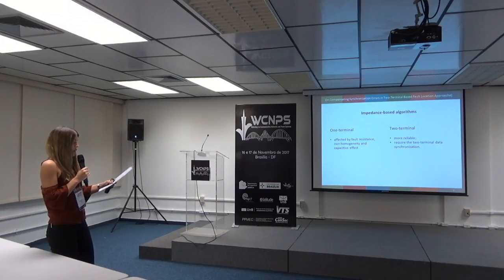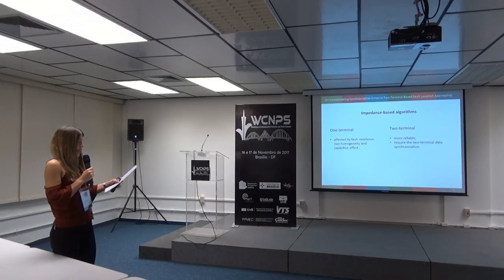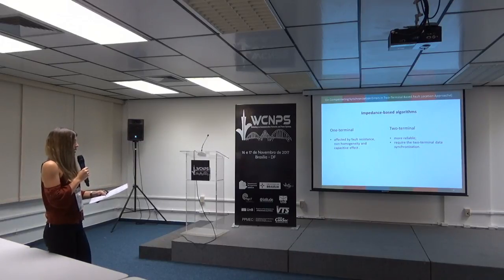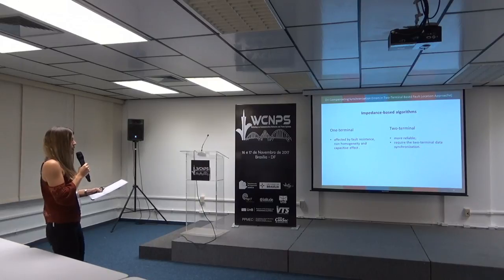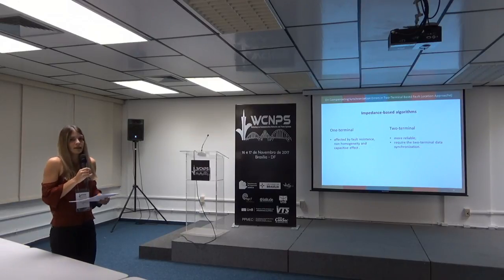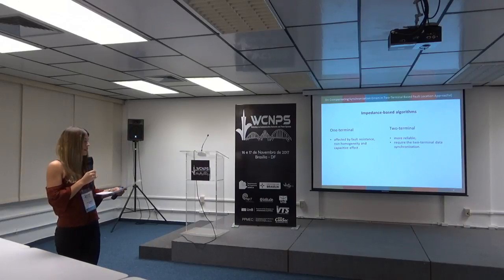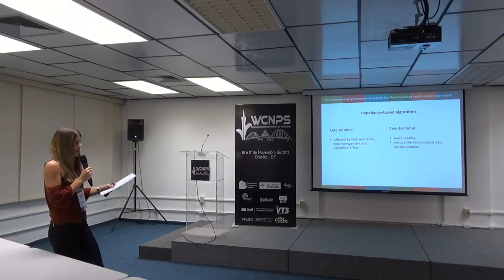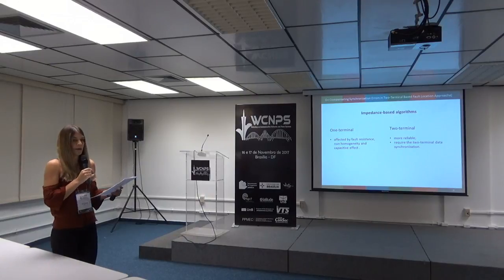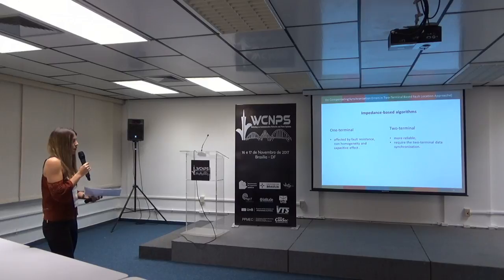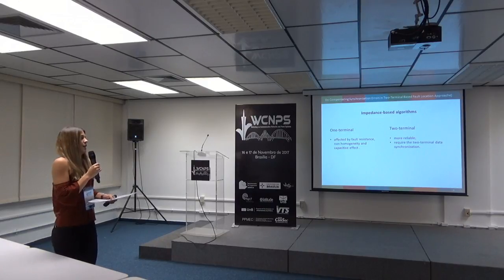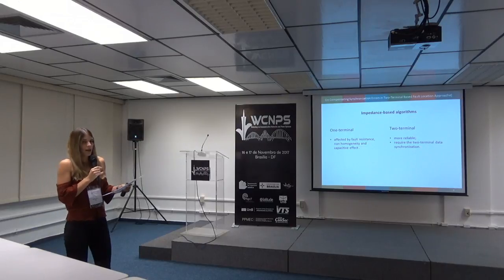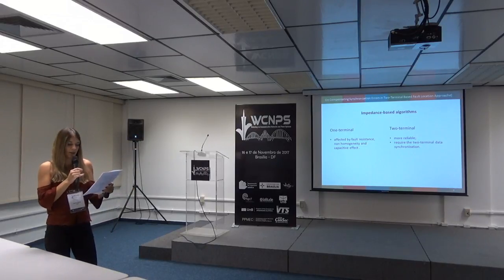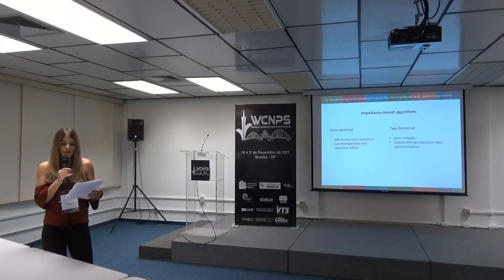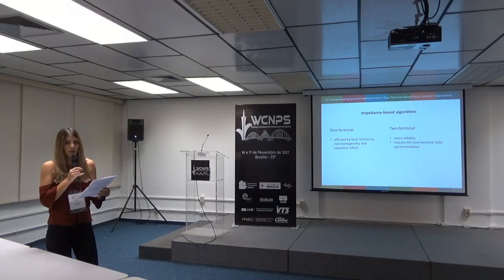Among the impedance-based fault locators, we can see two-terminal-based methods and one-terminal methods. The ones that use data from both line ends are commonly reported as the most reliable. These methods are not affected by fault resistance or homogeneity of the system, but they require synchronization. Although most growing research is looking for methods that don't need synchronization data. We can use GPS to do the synchronization, but in case of loss of the signal, the fault location procedure may be compromised.